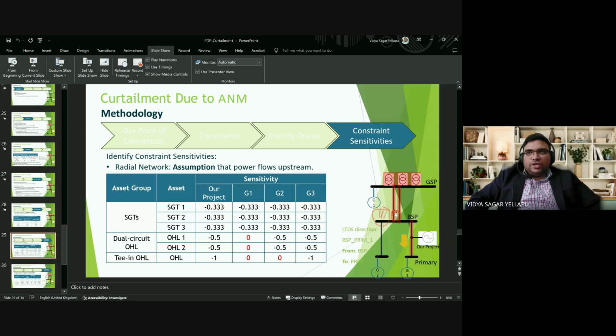Coming to the dual circuit OHL, if we consider generator G1, there need not be any sensitivity factor associated with this, because the generation from G1 is in no way concerned with these assets. If it is exporting, it goes through these SGTs and doesn't need to pass through these OHL assets. So generator G1 has a sensitivity factor of 0 and 0 for these assets. However, for G2 and G3, if there is an export, it is shared by these two equally, so 0.5, 0.5 for G2, and 0.5, 0.5 for G3 as well.